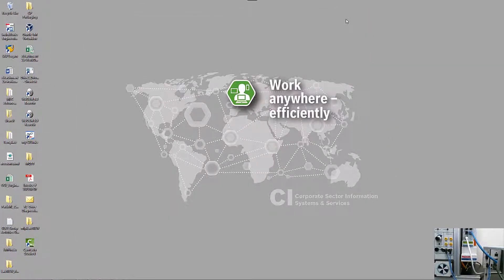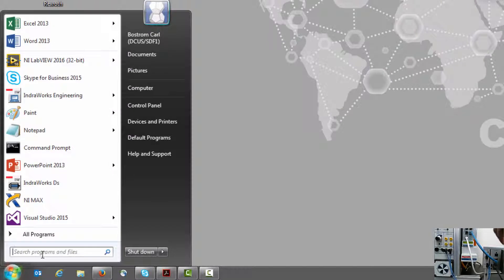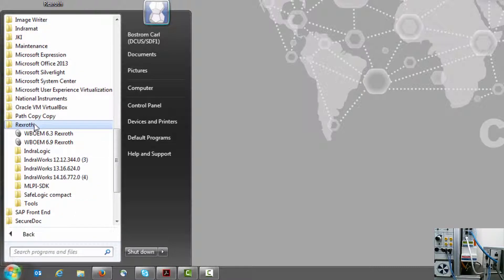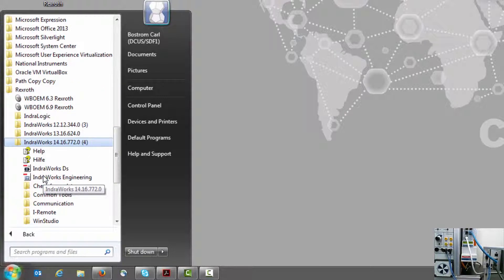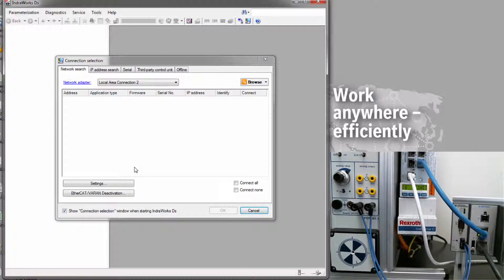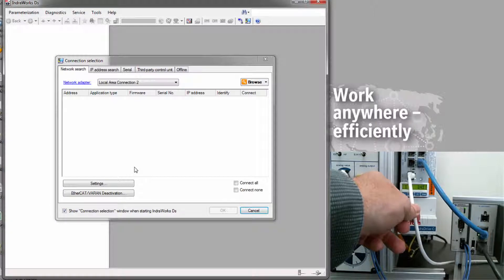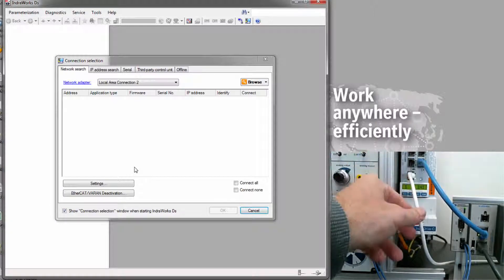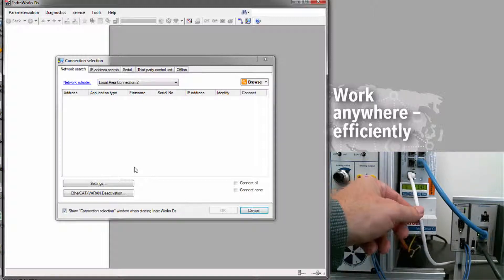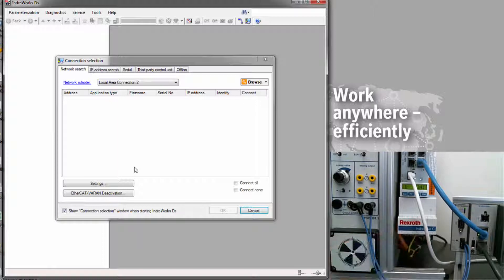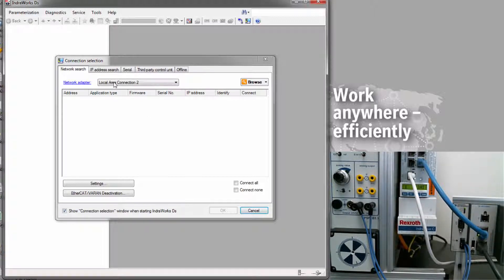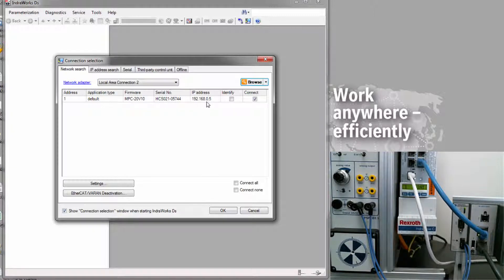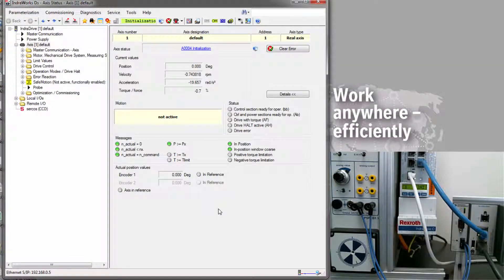Next, for the drive itself, we can configure the real-time port by opening up our commissioning software, which is called IndraWorks DS. IndraWorks DS is free software that you can download from the Internet. If you go to BoschRexroth.com, you'll find it there. Select IndraWorks DS. And again, I've made a physical Ethernet connection between my PC and the engineering port of the drive. This port is always labeled X26. On some of the drives, it's at the front panel. On other drives, it's actually underneath the drive itself. But once I've made that physical connection, I open up IndraWorks DS, click on the Network Search tab, select the adapter that I've used to make that physical Ethernet connection, and click Browse. The software should find the drive, regardless of the IP address of the drive itself. Make sure that Connect is checked here, and click OK. Now I have a connection to the drive.